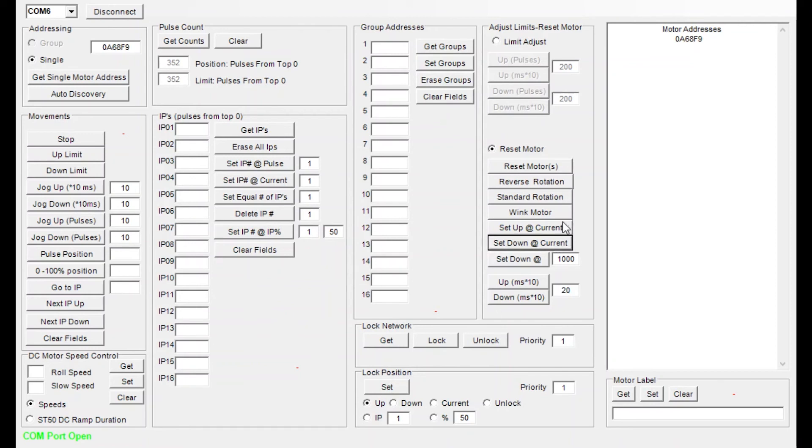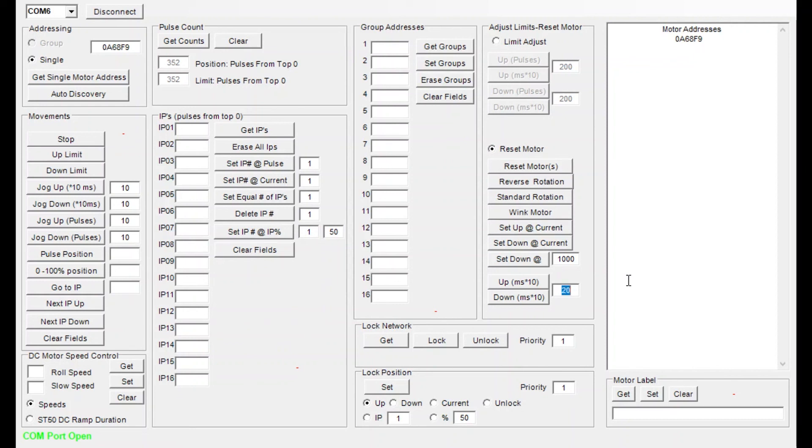We do the same with the upper limit. So again in this case we would send the motor up to its current limit. We would set our increment. In this case I'm going to go really small. And then we would simply use the up and down buttons to set that limit right where we want it and then click the set up at current. That is all that's required to change or even set new limits on that screen.